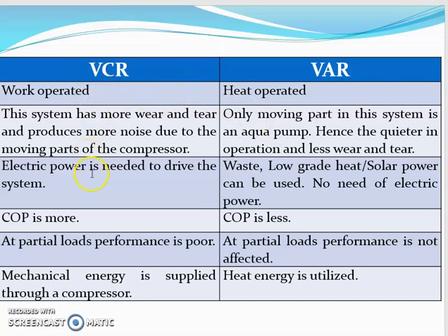In case of VCR, electric power is needed to drive the system, but in case of VR, waste or low grade heat energy can be used, so it doesn't need any electric power. In case of VCR system, its coefficient of performance is quite better compared to vapor absorption refrigeration system. In case of VCR, part load performance is poor, but in case of VR system, part load performance is not much affected. In case of VCR system, we need to supply mechanical energy to run the compressor, but in case of VR, we are utilizing waste heat energy to run the generator.